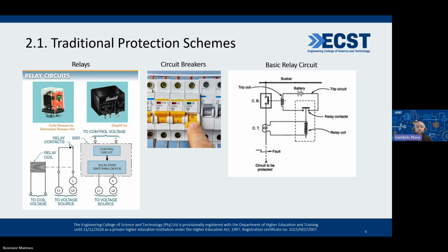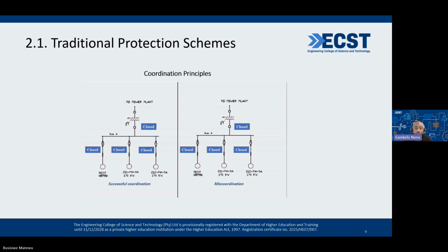Hence, if you think of coordination principles, things like selectivity are very important. Selectivity, sensitivity, and also stability. Your protection system should be selective as to whether the fault is occurring within its protection zone or outside its protection zone, and speed is also very important. Obviously, there will be a time for the relay to respond. Normally, I think it's about 4 milliseconds, right?